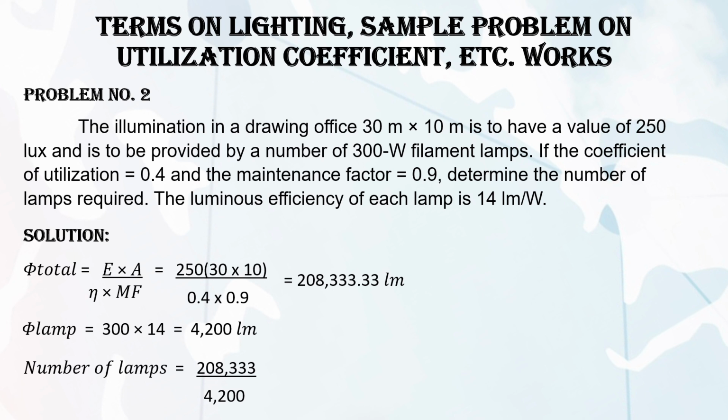So, atong equate. Ang answer nato is 208,333.33 lm divided by 4,200 lm, which is equal to 49.60. And then kung atong i-round up, a total of 50 lamps. So that is the final answer.